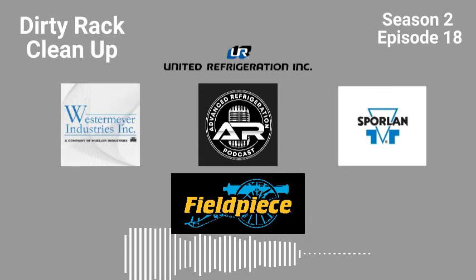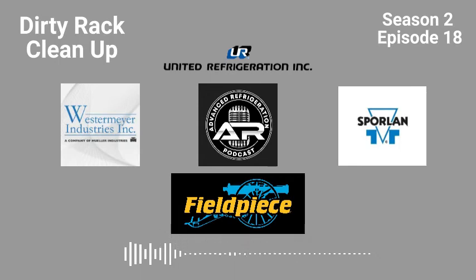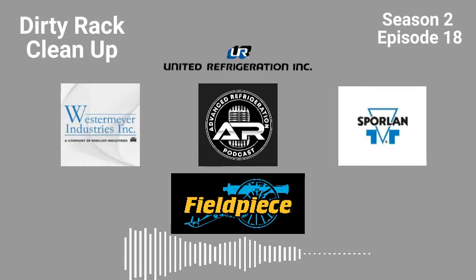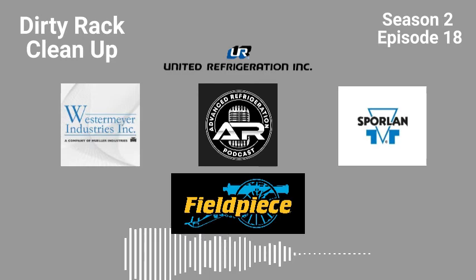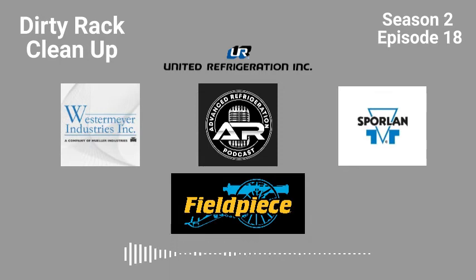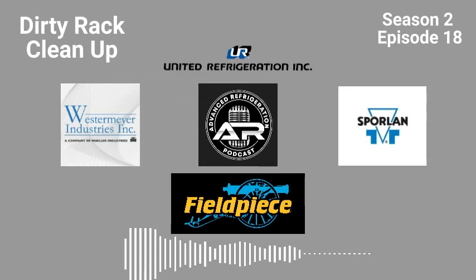I've had a bunch of liquid canister filters where the centerpiece, I'm not sure what they call it, but basically the strainer in the center, blows out. Or the newer ones break when people crank down on them, the newer style Sporlan ones. If you crank down real hard, that's just a pressed fitting in the end where the screen is, so it'll pull right out. Really? No, the problem we were having was just bad, dirty systems, eating shit and causing a ridiculous amount of blockage in them. You can get those screens at United. You buy a pack, I think they come in a pack of 10 from Sporlan. You can buy the screens for the older strainers and the Danfoss ones.